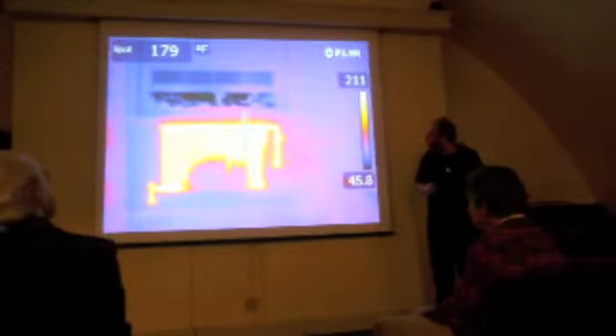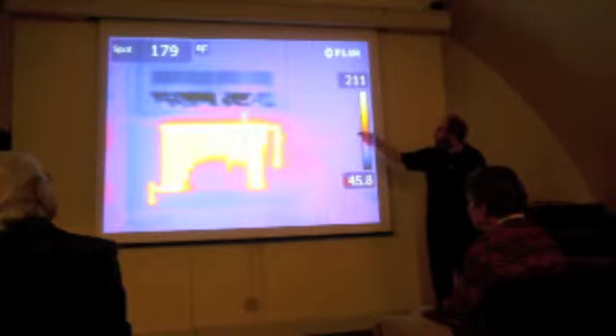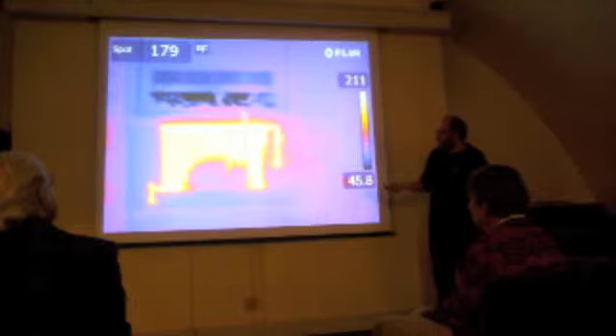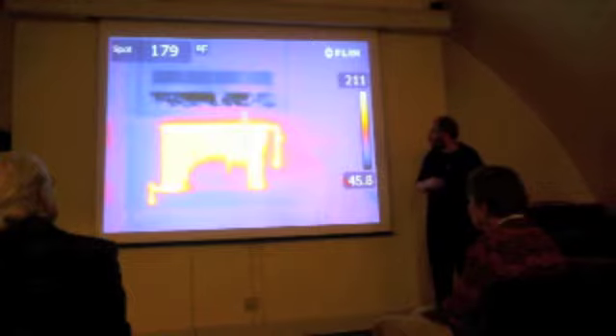And then when you look at the radiators themselves, they're 210 degrees, largely using steam, but you can see that a whole big chunk of it has been blocked off and there's no more steam flow through the system, so only about two-thirds of it is actually heated. There are lots of neat ways that you can really low-cost retrofit.